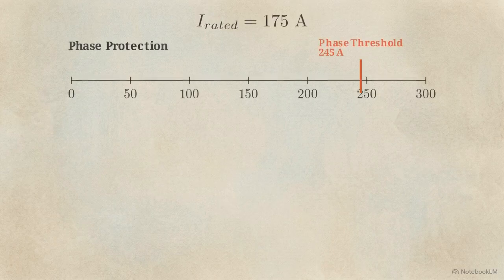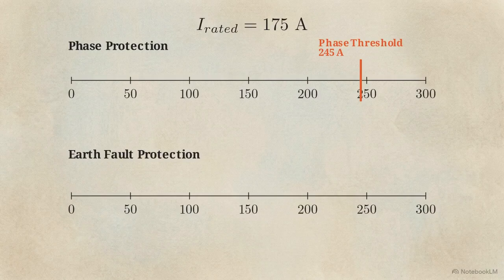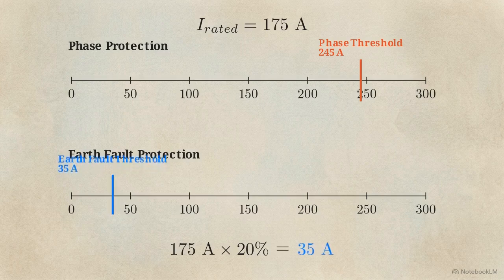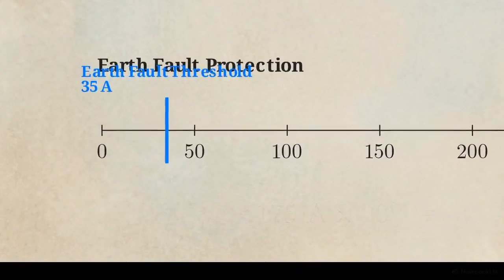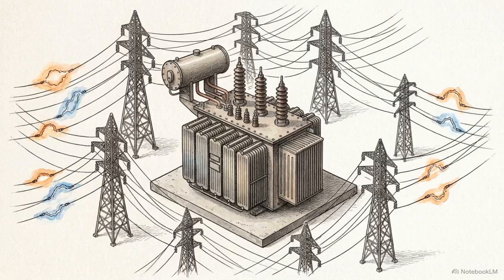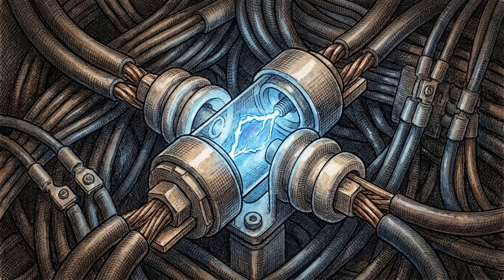To detect this, we calculate an independent earth fault setting. Because normal earth current should be near zero, we tighten the sensitivity dramatically to just 20% of rated current. This gives us a primary threshold of only 35 amps, which scales down to a tiny 0.875 amp secondary trigger at the relay. By utilizing layered time current curves and tight earth fault thresholds, the transformer acts as a selective cooperative node in the power grid, targeting specific anomalies rather than reacting blindly to every surge.